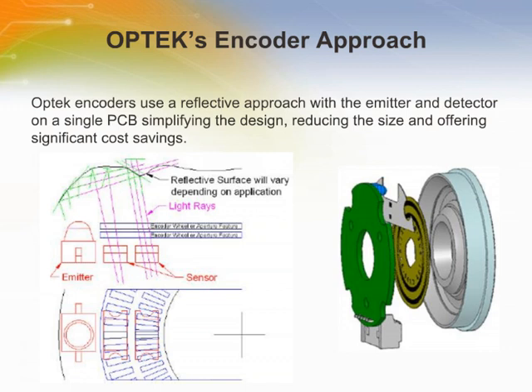A light beam interrupted by a rotating code wheel is the essence of an optical shaft encoder. The light beam produced by an LED is transmitted through a code disk with an alternating opaque and transparent pattern. The code disk is fixed on the motor shaft. Small sensors like phototransistors or photodiodes measure the light modulation.